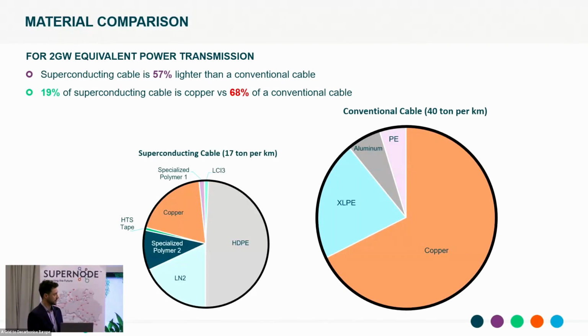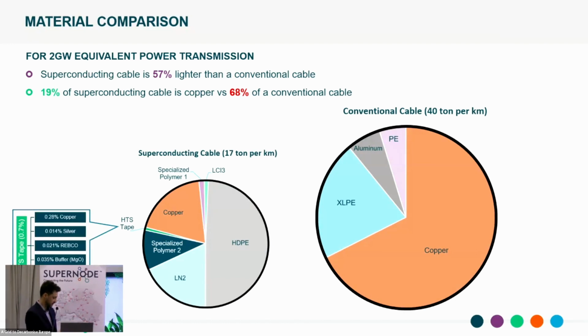The equivalent in a SuperNode cable is presented here. It's about half the weight, much more compact. You can see straight away we're not using much commodity metal such as copper - we have a small amount, but not much. Mainly the cable is comprised of low-cost polymers, so high-density polyethylene or cross-linked polyethylene, and some liquid nitrogen, which is inert, abundant and cheap. The superconducting material itself is just this small green sliver, a very small part of the cable, which makes it very scalable. If we want to increase the power capacity of the cable, we just need to increase the amount of tape.